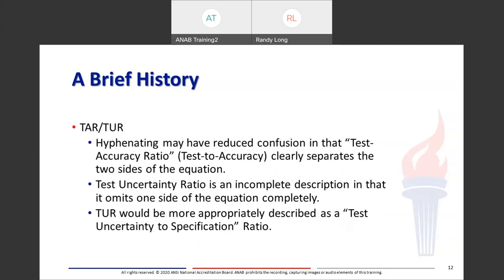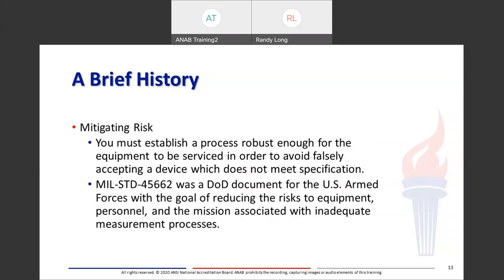TAR and TUR: hyphenating may have reduced the confusion — 'test-accuracy ratio' clearly separates the two sides of the equation. Test uncertainty ratio is an incomplete description in itself in that it omits one side of the equation completely. TUR would be more appropriately described as test uncertainty to specification ratio. The military used to love acronyms, and they still do.